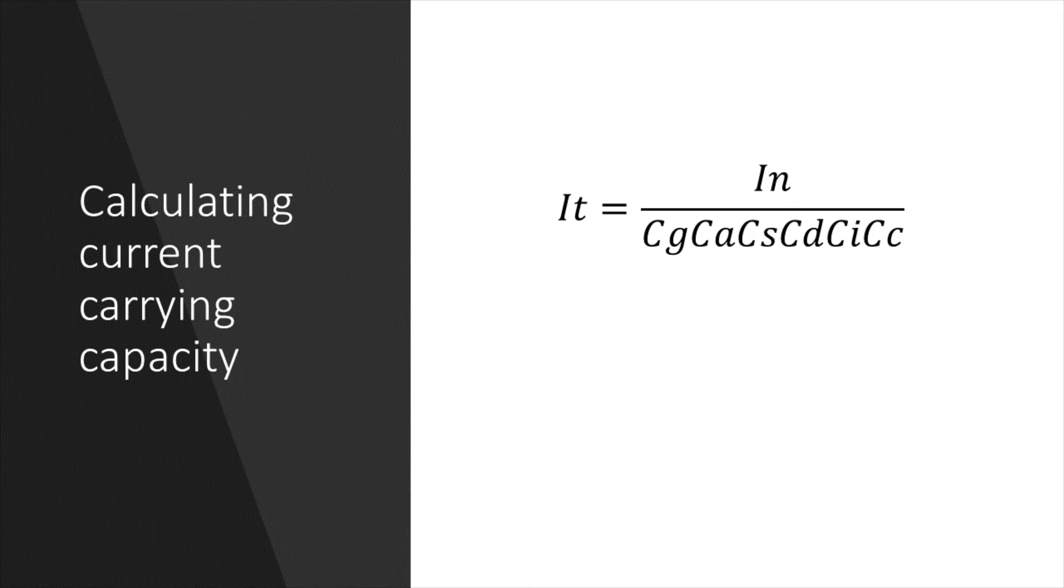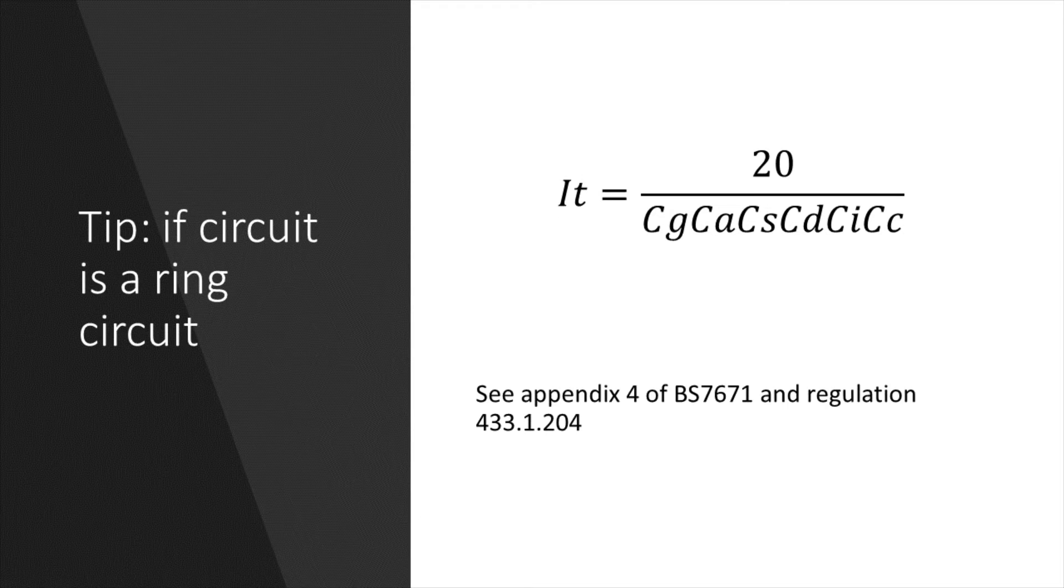However, as I mentioned earlier, there are a couple of exceptions to this. The first is when it comes to ring socket circuits. If you install a ring socket circuit wired in 2.5mm cable and protected by a 32-amp protective device, as described in Appendix 15 of BS7671, in that situation the protective device rated at 32 amps is greater than the rating of the 2.5mm cable. The reason for this is explained in Regulation 433.1.204.